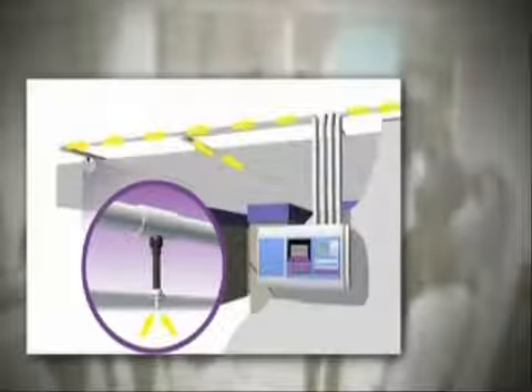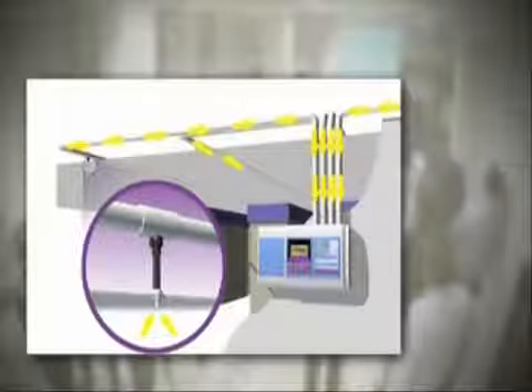This is an active detector using a network of pipes to continually draw air from a protected area. The second detector is a conventional point or spot detector that uses passive technology. The detectors are installed in 4 commonly protected areas as prescribed by codes and fire risk assessors. The ceiling for general area detection, across the air conditioning return air grill, in-duct and cabinet detections are used to detect smoke that originates from smouldering electrical components. There are 3 different fire detection designs to suit 3 different cabinet styles.